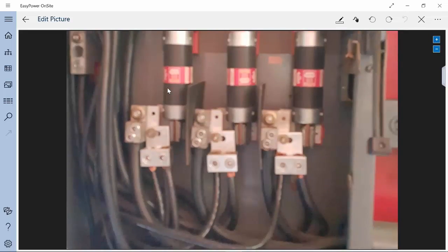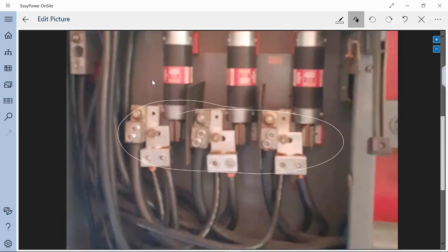And rather than just the one cable I was expecting to go to the main distribution panel, I see at least two others here. So in effect, what the original construction team did was utilize this particular termination point as a bus. And I want to recognize that as I connect the dots in the tablet. So let's save this and then carry these through to my note.